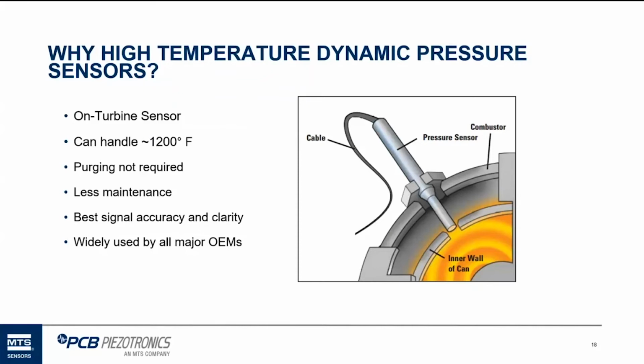There's no purging necessary. Those other systems, specifically the remote, those systems need to be purged with nitrogen on a regular basis, and that's not real convenient. I've seen a lot of plants out there over my time where they run out of nitrogen and nobody knows, and the tanks are empty. Nobody's watched it. So what happens in those tubes, if they aren't purged with nitrogen on a regular basis, they start to get moisture inside and can give them some really, really ugly looking readings coming out of that.